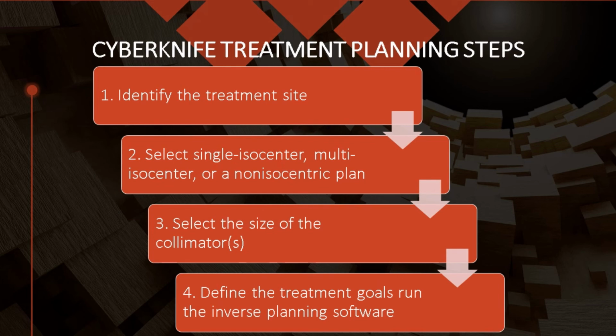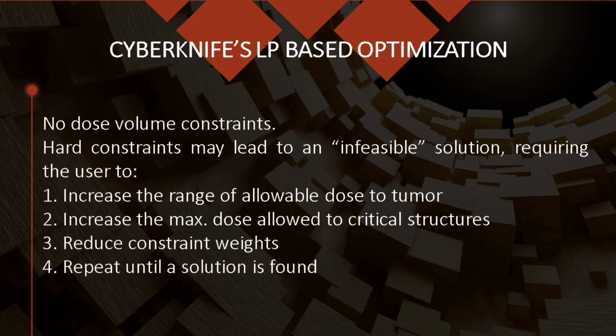3. Select the size of the collimators. For most cases, a collimator diameter is chosen that is equal to approximately 75% of the lesion's smallest projected cross-section. And 4. Define the treatment goals. Run the inverse planning software. Cyberknife's LP-based optimization has no dose volume constraints. Hard constraints may lead to an infeasible solution, requiring the user to increase the range of allowable dose to the tumor, increase the maximum dose allowed to critical structures, and reduce constraint weights, repeating until a solution is found.